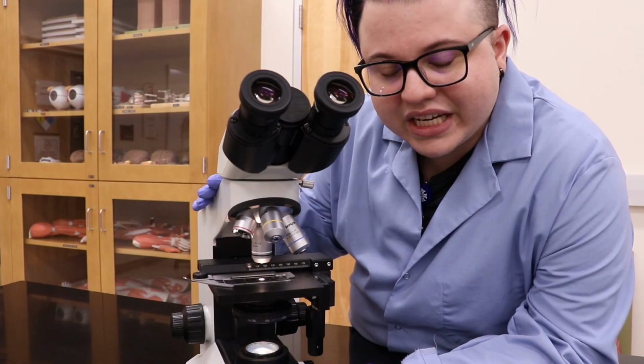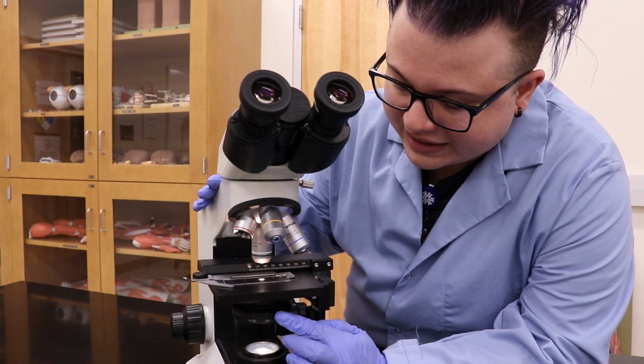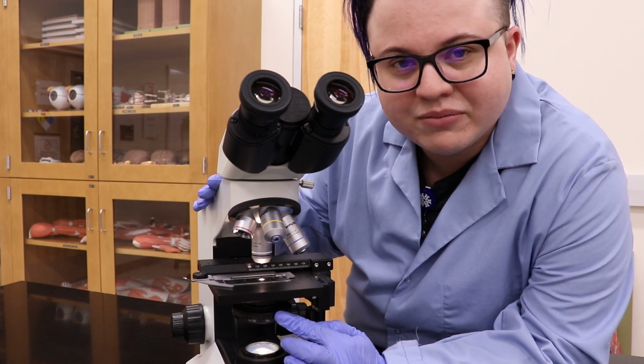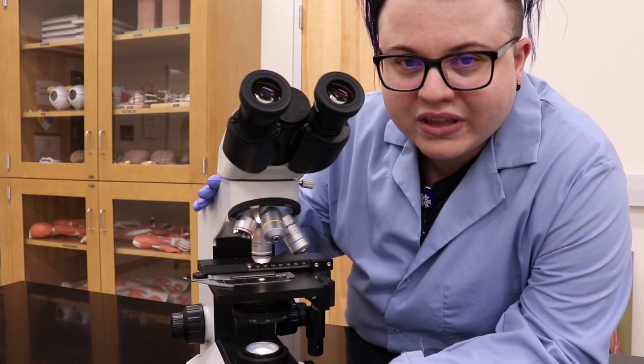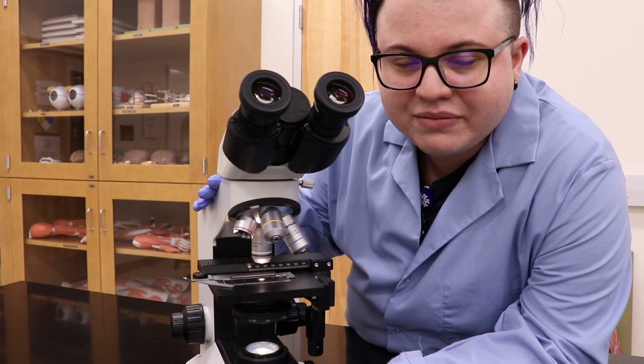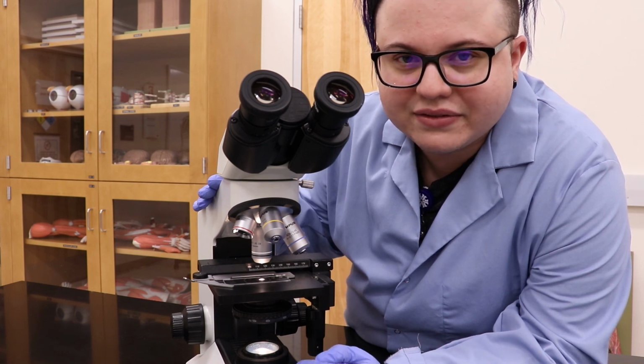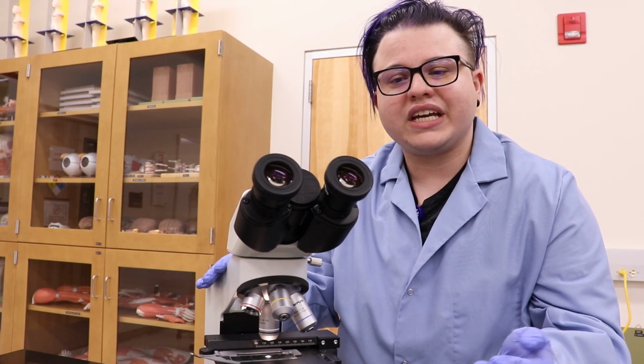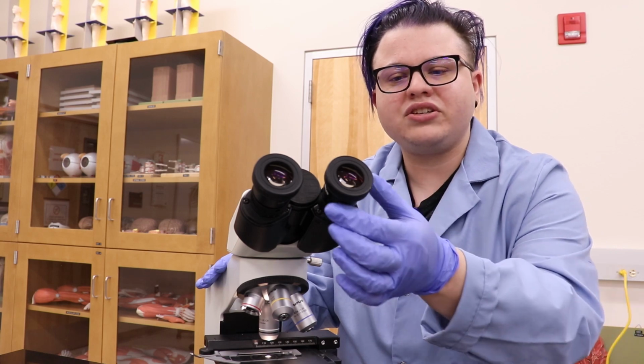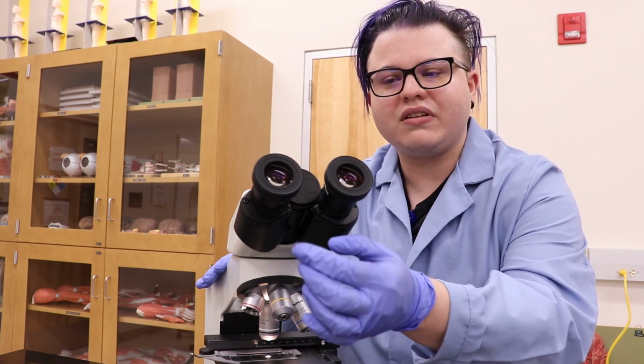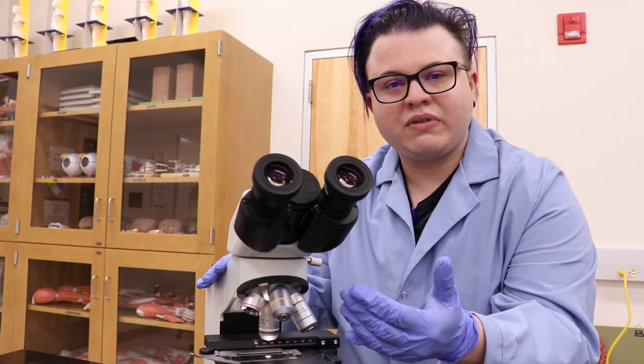The first thing you can check is to make sure that the diaphragm is set to the proper light level for the objective that they're using. That'll make sure that they have enough light going through to be able to see anything through that objective. The next thing you can check is to make sure that the diopters, which you can find on the eyepiece itself, are even or pushed all the way in.